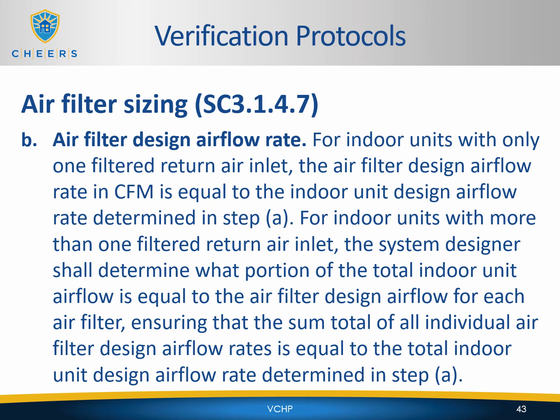For indoor units with more than one filtered return air inlet, the system designer shall determine what portion of the total indoor unit airflow is equal to the air filter design airflow for each air filter, ensuring that the sum total of all individual air filter design airflow rates is equal to the total indoor unit design airflow rate determined in Step A.